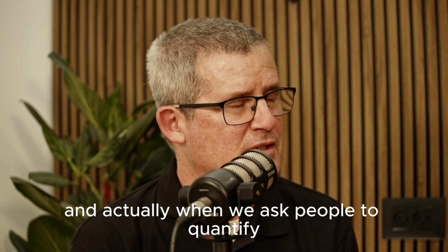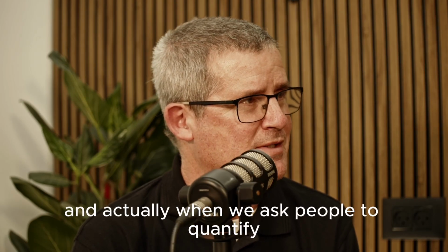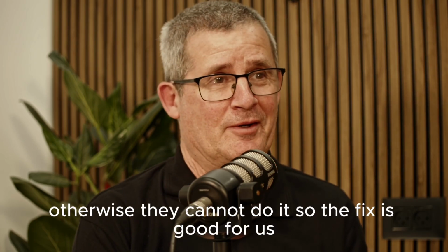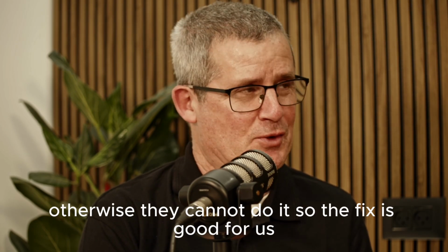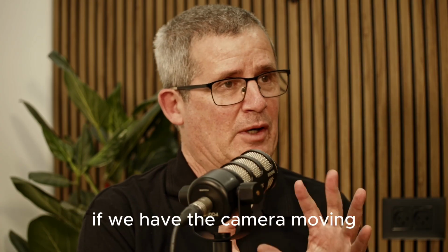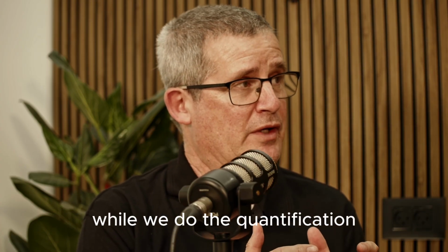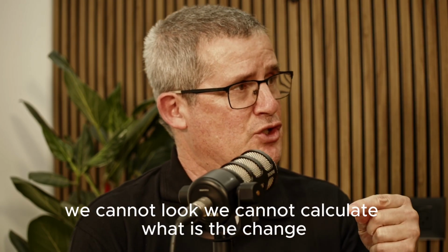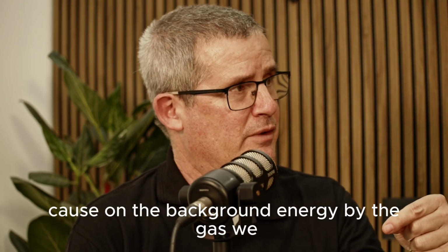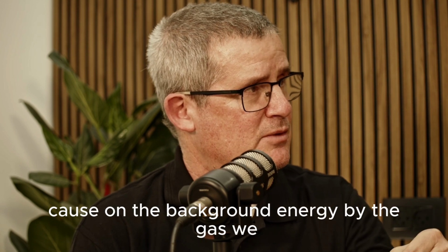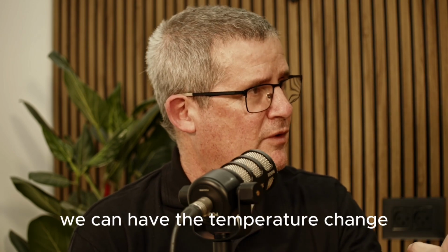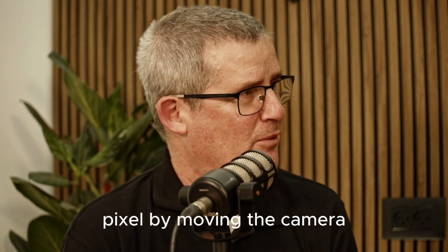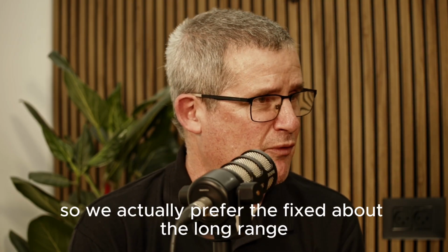For me, on the fixed, when we ask people to quantify, we ask them to put it on a tripod. Otherwise, they cannot do it. So the fixed is good for us. If we have the camera moving while we do the quantification, we cannot calculate the change caused on the background energy by the gas. We can have a temperature change because we move the background pixel by moving the camera. So we actually prefer the fixed.